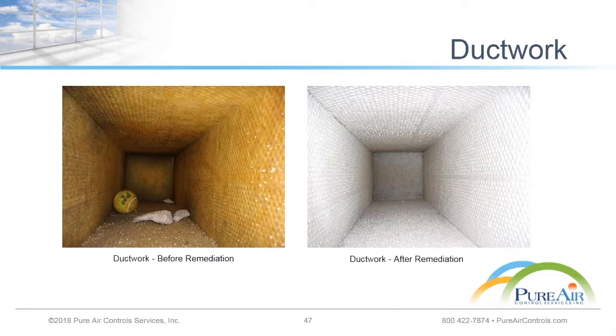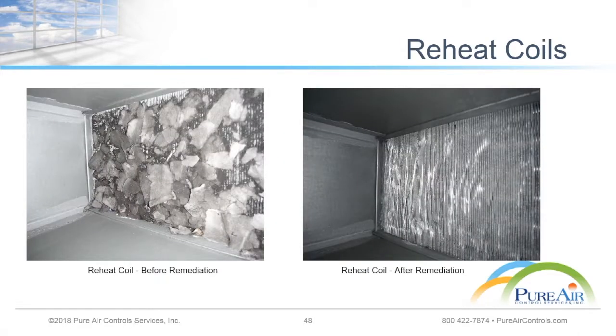This is a big deal too, where people often don't think of the entire system as a whole, even if they're doing a one-for-one swap with a new unit but not redesigning the ductwork or anything that unit's attaching to. These reheat coils - reheat coils in the supply, and the VAVs in the supply ductwork, can become extremely debris filled and clogged. So that's just an example there of that situation.